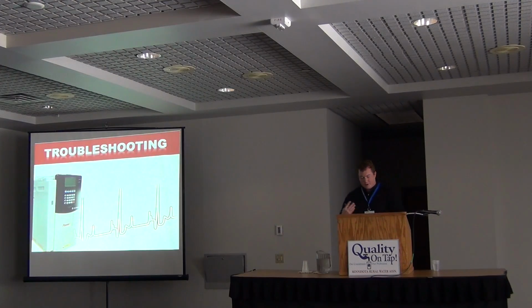Back to cooling again. Is proper cooling present? Is it still working? Is the input side of my cooling clogged? Is the AC still working? What's it set at? Is it sized correctly? And you have to understand your load. Without a load, there's no reason for the drive and the motor. If I have a 40 horsepower drive on a 40 horsepower motor that's pushing against nothing, it's not going to draw 40 horse. It's going to draw like 5, whatever it costs to overcome the moment of inertia within the motor. So your VFD isn't going to be pushing hard, and it's not going to be putting off as much heat if there's no load.